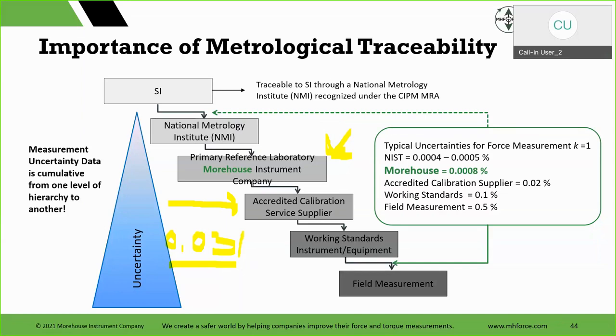But typical uncertainties, here you can see them. NIST, this is K equals one. That's one standard, it's standard uncertainty. Accredited cal supplier, working standards, field measurements. And you can start seeing some of these. You know, if they're at 0.02, the best they can give you is 0.03 under the best conditions. And as I said, it just doesn't happen.